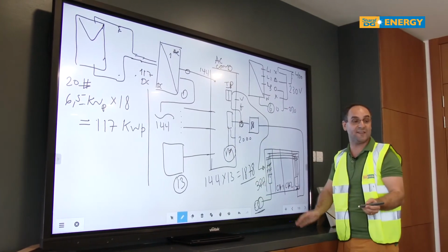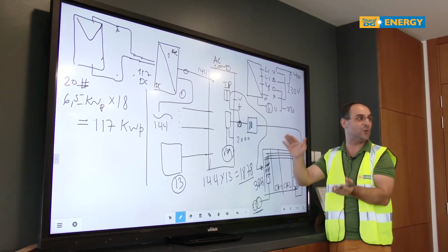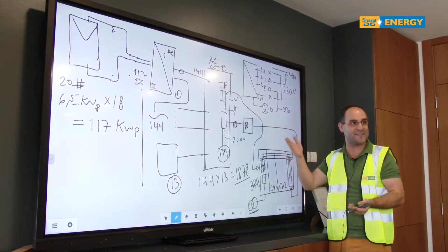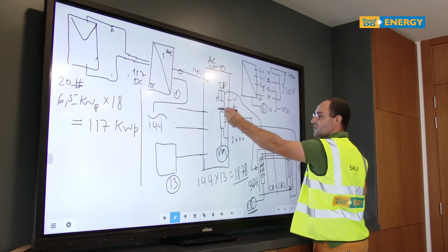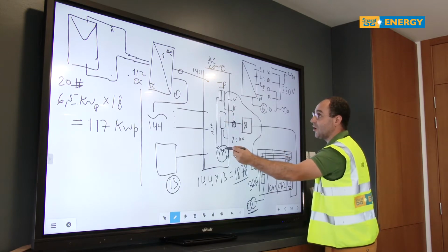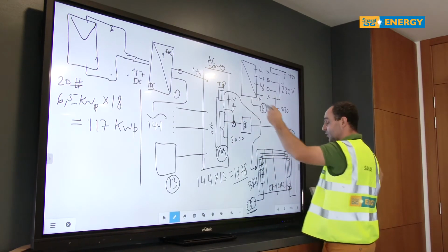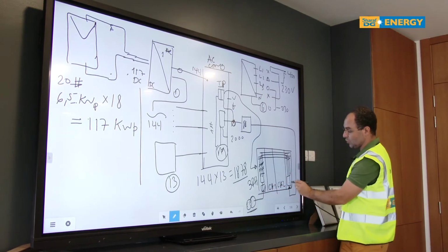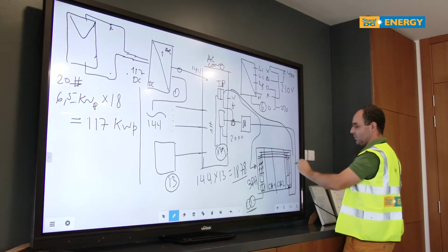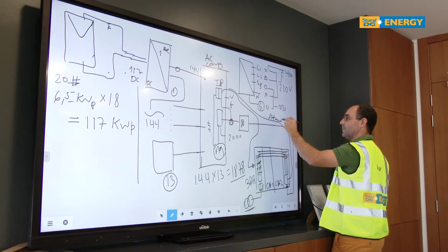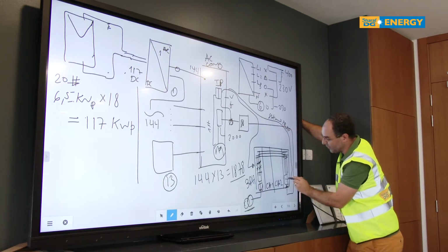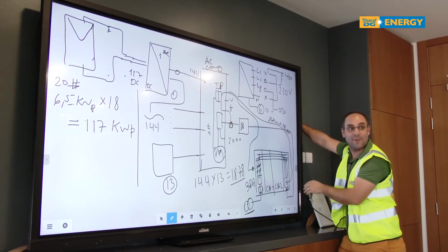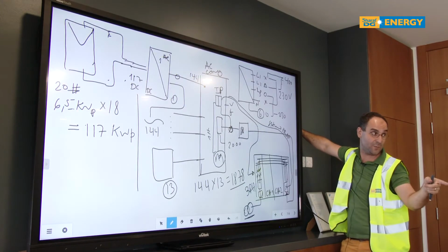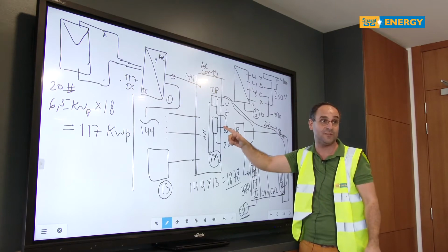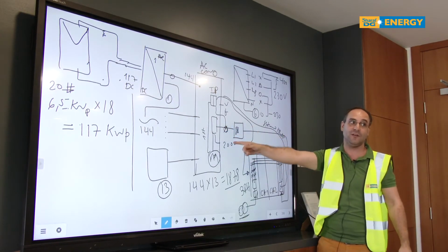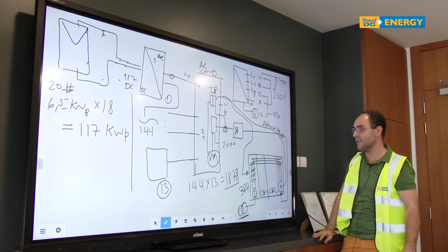But this is motorized, in the sense that if the conditions are restored, it will automatically close the circuit again so you can synchronize again. If this first order is not acknowledged within a quarter of a second, a second order will come to the solar breaker, like a shunt trip, to open this machine. But if this one opens, this one needs to be manually reset. If it opens, an operation team, for example, will know that this guy did not respond, so you may need to see or call someone to come and check the problem. But that's your protection.